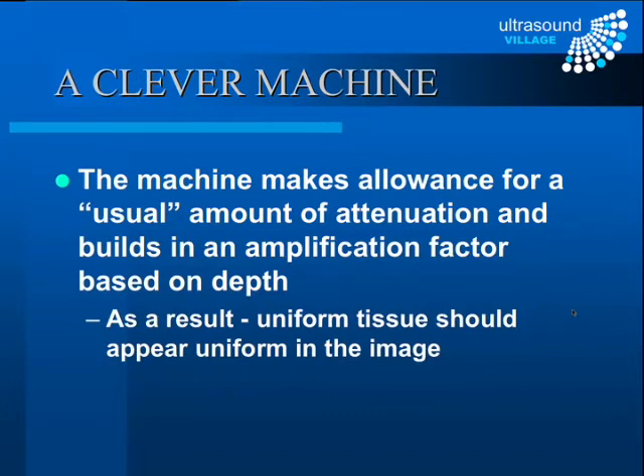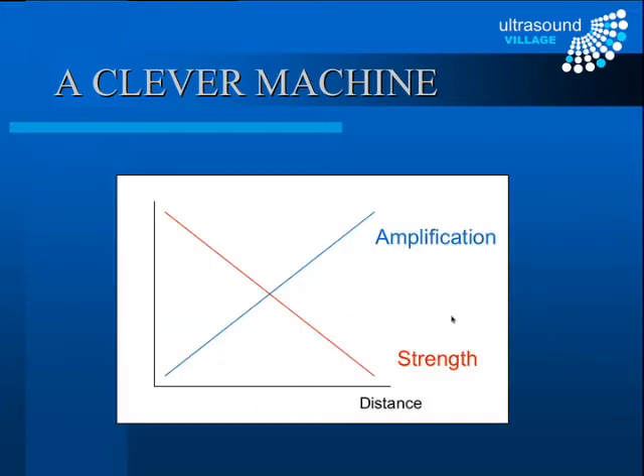The machines themselves are very clever. We've already spoken about attenuation — the tissue absorbs and dissipates energy. The machine actually accounts for this by building in an amplification factor based on depth, which it knows from the return signal time. The result is that a uniform tissue should appear uniform in the image. A blip returning quickly receives only a small amplification, while a blip that takes much longer to return is amplified a great deal more to compensate for that attenuation.